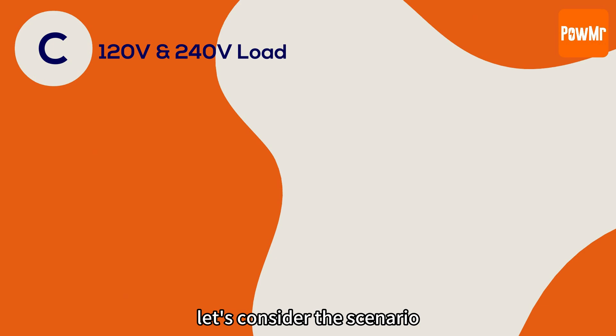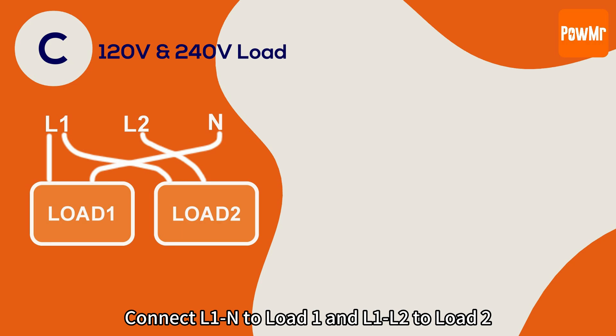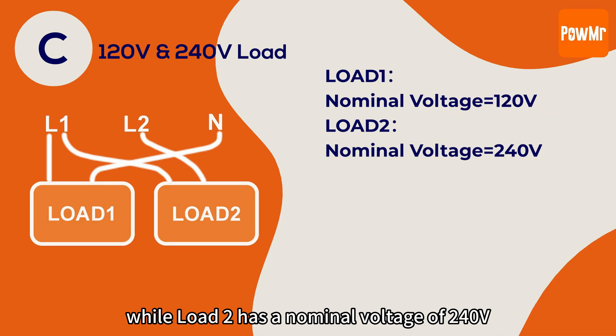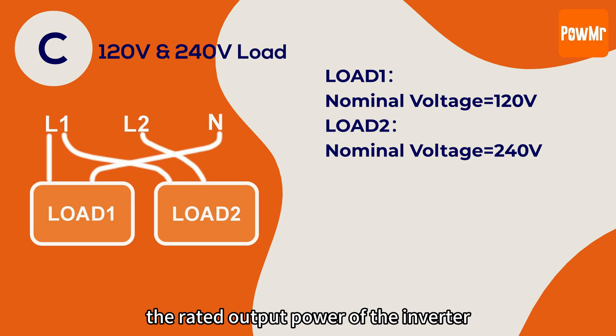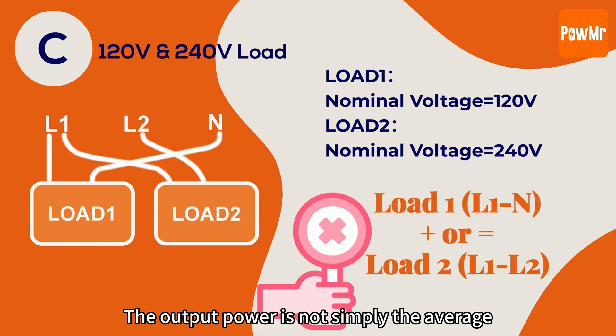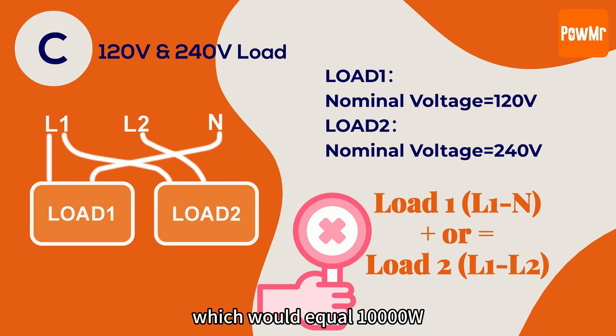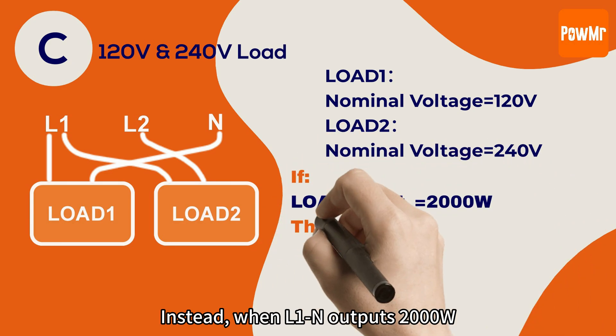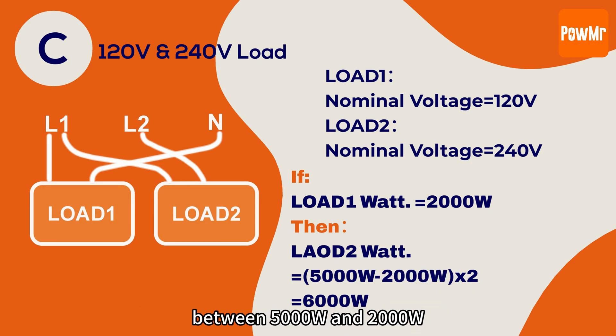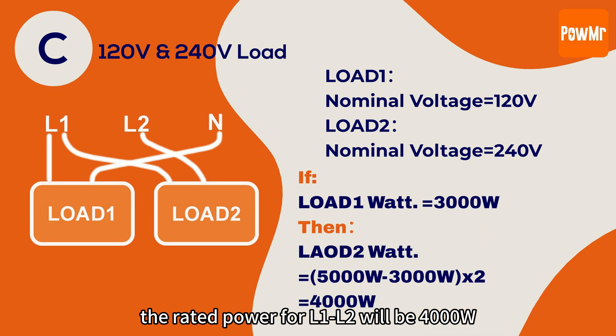Finally, let's consider the scenario where both 120V and 240V loads are connected. Connect L1N to load 1 and L1-L2 to load 2. In this case, load 1 has a nominal voltage of 120V, while load 2 has a nominal voltage of 240V. However, the rated output power of the inverter will differ from the previous two output modes. The output power is not simply the average or sum of the rated power of load 1 and load 2. Instead, when L1N outputs 2,000W, the L1-L2 output power will be twice the difference between 5,000W and 2,000W. Similarly, if a 3,000W load is connected to L1N, the rated power for L1-L2 will be 4,000W.